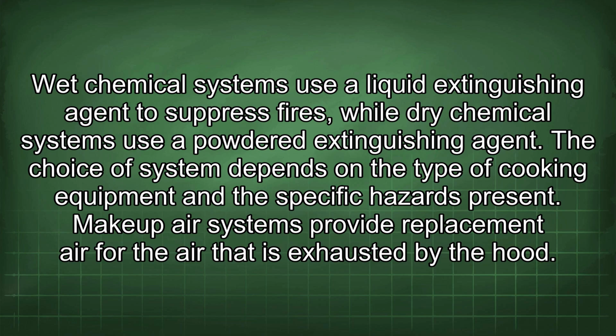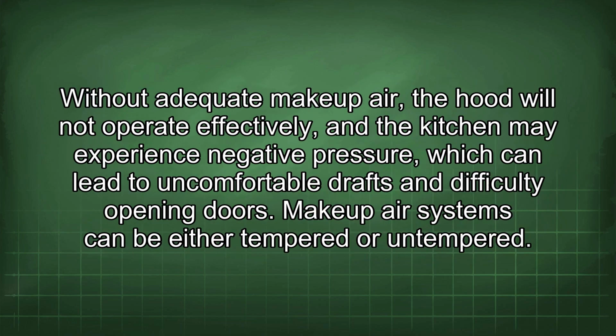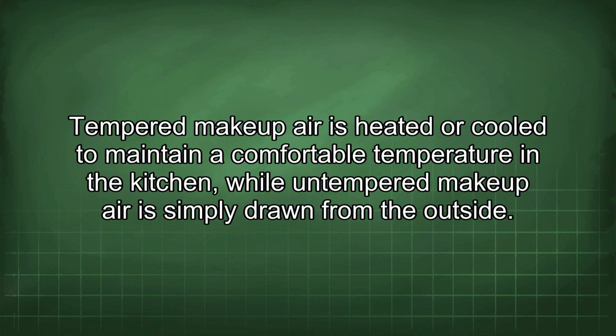Makeup air systems provide replacement air for the air that is exhausted by the hood. Without adequate makeup air, the hood will not operate effectively, and the kitchen may experience negative pressure, which can lead to uncomfortable drafts and difficulty opening doors. Makeup air systems can be either tempered or untempered. Tempered makeup air is heated or cooled to maintain a comfortable temperature in the kitchen, while untempered makeup air is simply drawn from the outside.